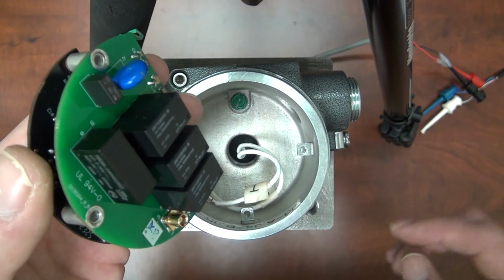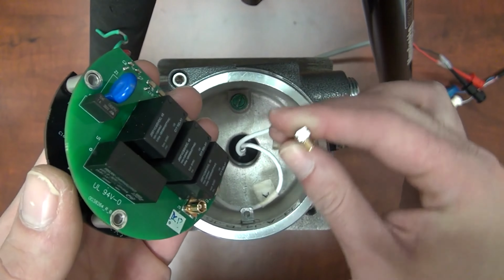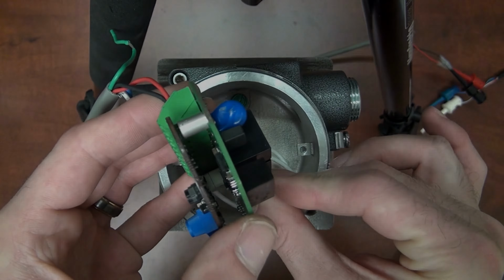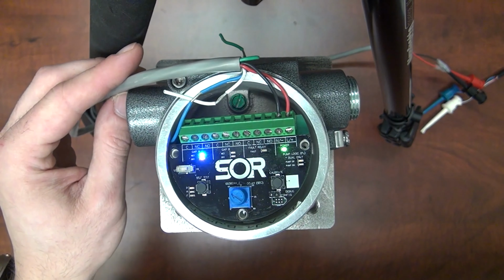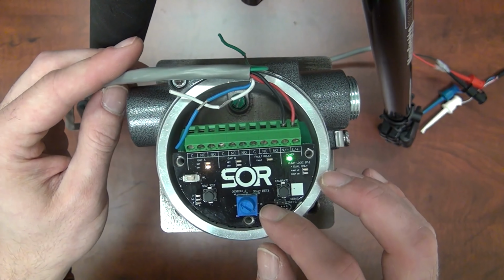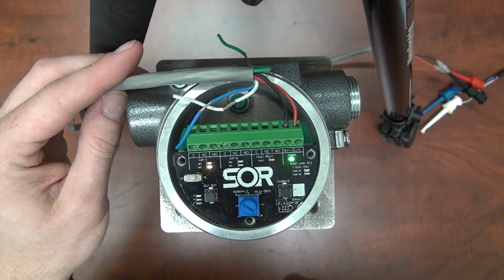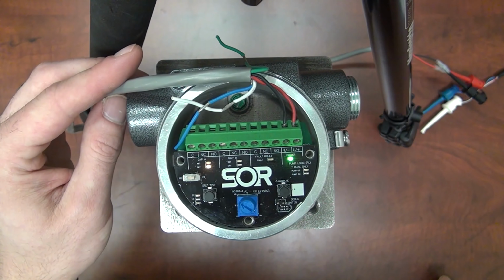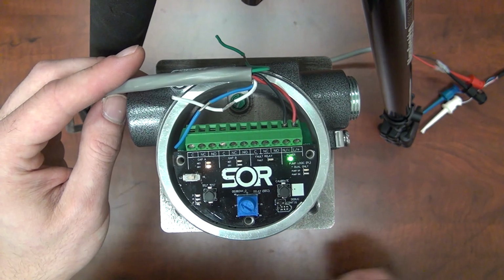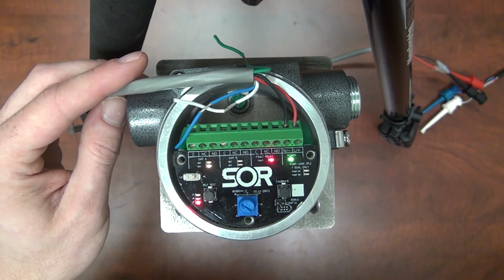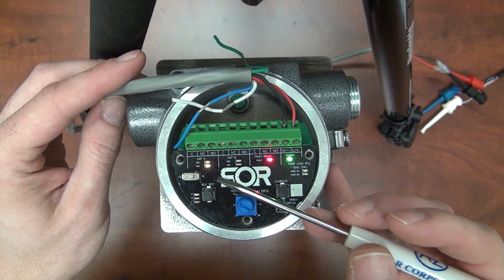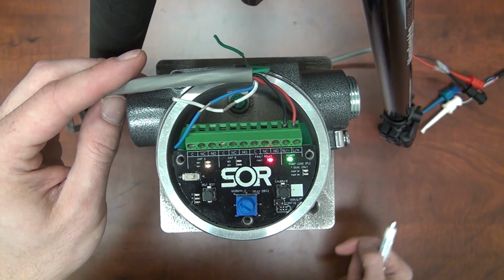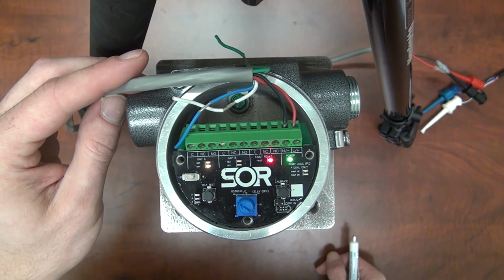Let's now plug the T connector into the back of the board. After restoring power to the device, it will go back into its normal operating state. When we press the self-test button again this time, it will now show us the second failure, that being the A cable disconnected. This will be seen as flashing dry LEDs and the red fault LED flashing.